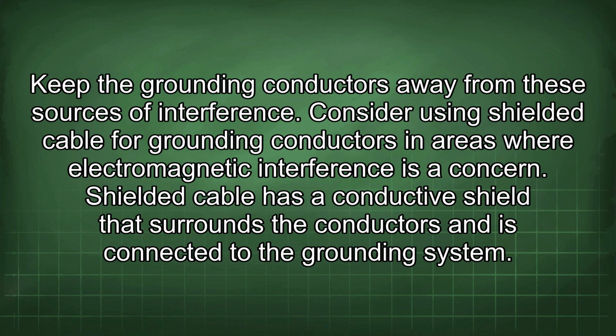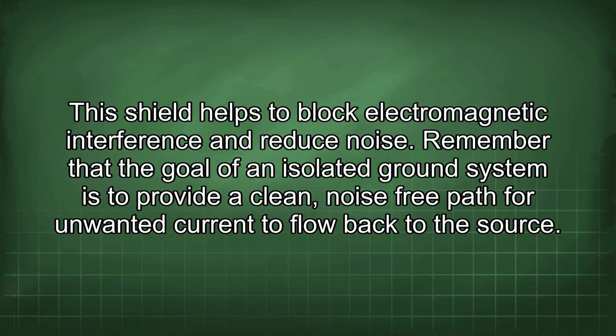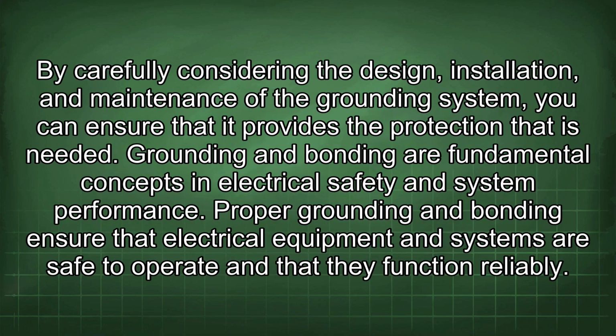Shielded cable has a conductive shield that surrounds the conductors and is connected to the grounding system. The shield helps to block electromagnetic interference and reduce noise. Remember that the goal of an isolated ground system is to provide a clean, noise-free path for unwanted current to flow back to the source.